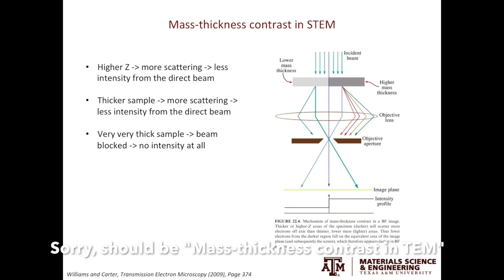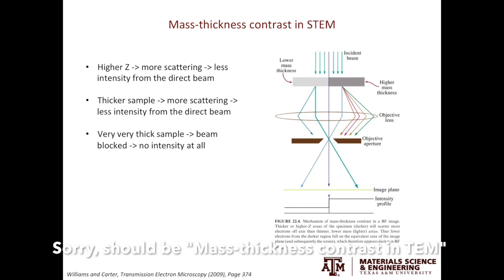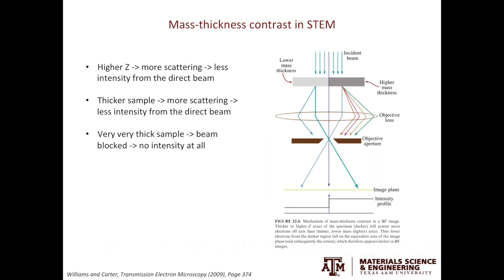The origin of mass thickness contrast really comes from the scattering theory we learned earlier. For higher Z samples, they scatter electrons more strongly, therefore there's less intensity in the direct beam, and they will appear darker in the image. Similarly, for thicker samples, there is also more scattering and less intensity from the direct beam, and they will appear darker. If the sample is super thick, the electron beam will not be able to go through, and there will be no intensity at all.